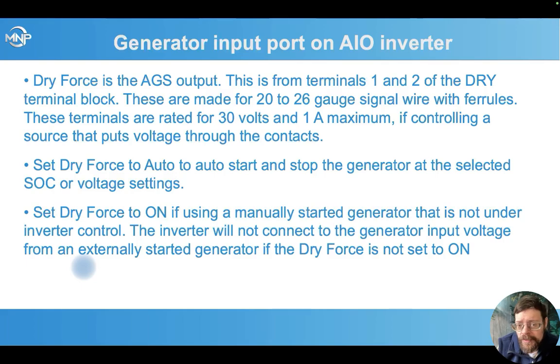These terminals are rated for 30 volts and 1 amp maximum. So most generators are just doing a sense whether those terminals are connected or not, but some generators will output voltage through those contacts, so you need to think about what voltage is that. If it's sending a 12 volt signal through there, that's probably fine. Every once in a while we'll find one that's sending a 20 or a random voltage through there, or even 120 volts AC through that contact. So just because you've got a 2-wire start generator, think about what exactly is going on and whether you might need an intermediate relay in between there if it's putting voltage back on those contacts that's more than what they're rated for.